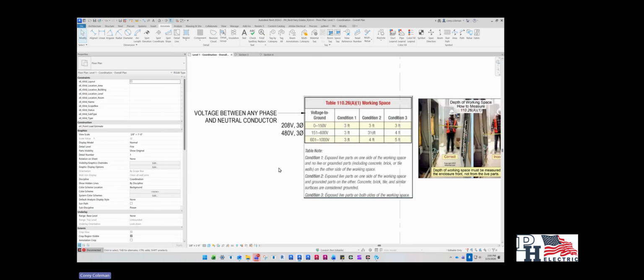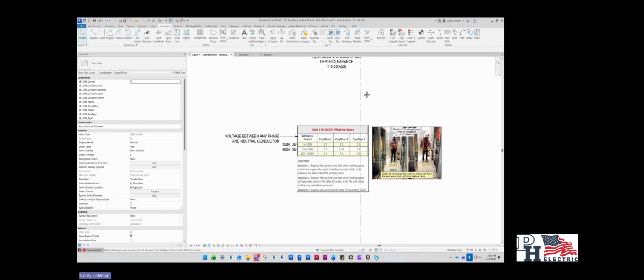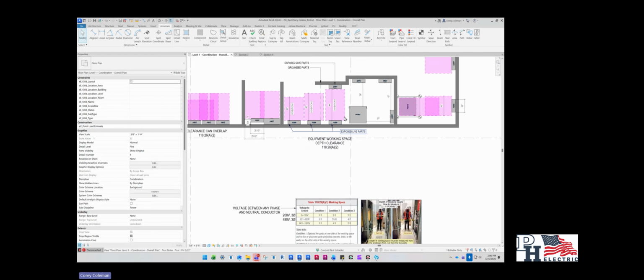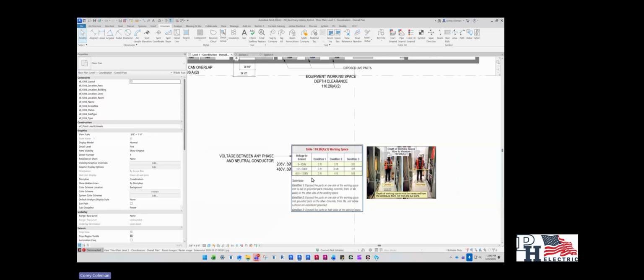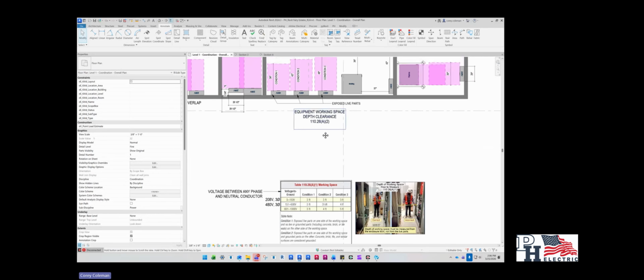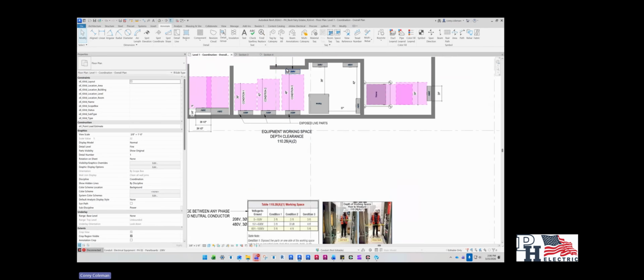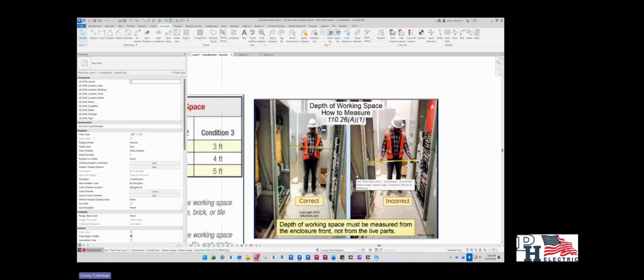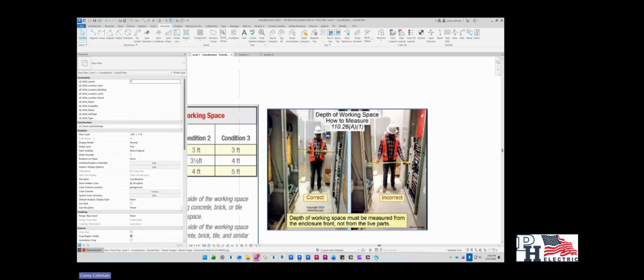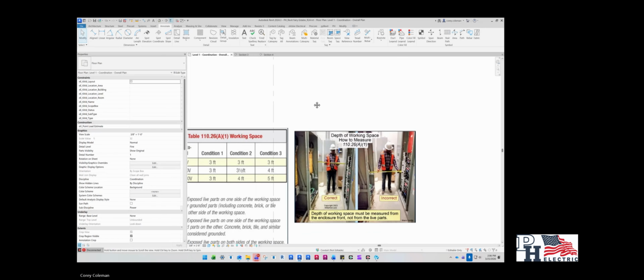And that is all based on Table 110.26(A)(1) working space. The first is based on voltage, so your 208 volt panels live in row 1. Your 480 volt panels will live in row 2. And this is the definition of how far they need to be. So in this space here, we have 480 volt panels, and you can see that each one follows the condition based on what is in front of them: either grounded parts, non-grounded parts, or exposed live parts. When you're measuring exposed live parts, you're going to be measuring from the face of the equipment to the face of the equipment, not from the bus to the bus. Just so everyone's aware.